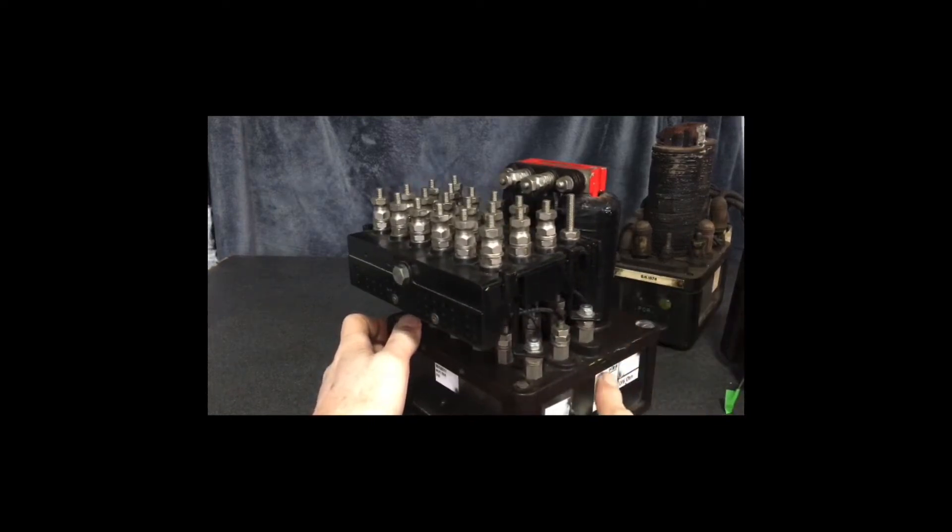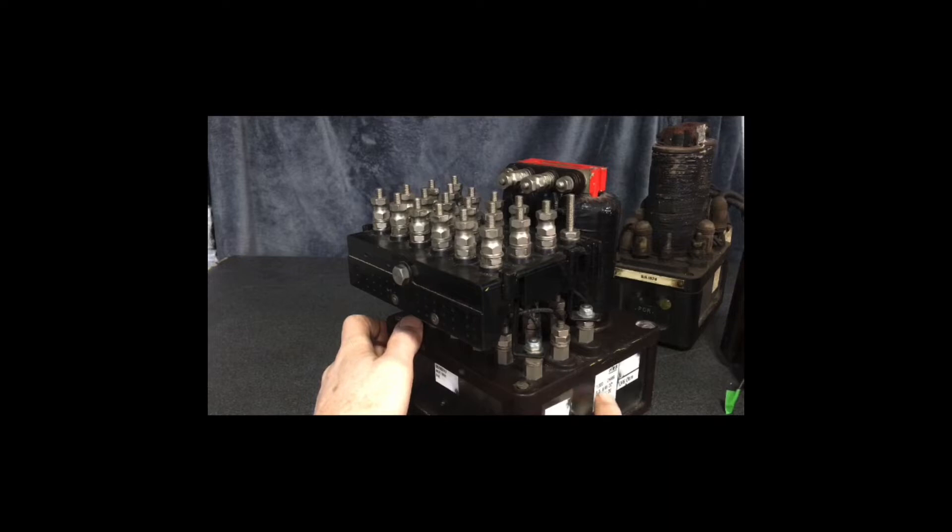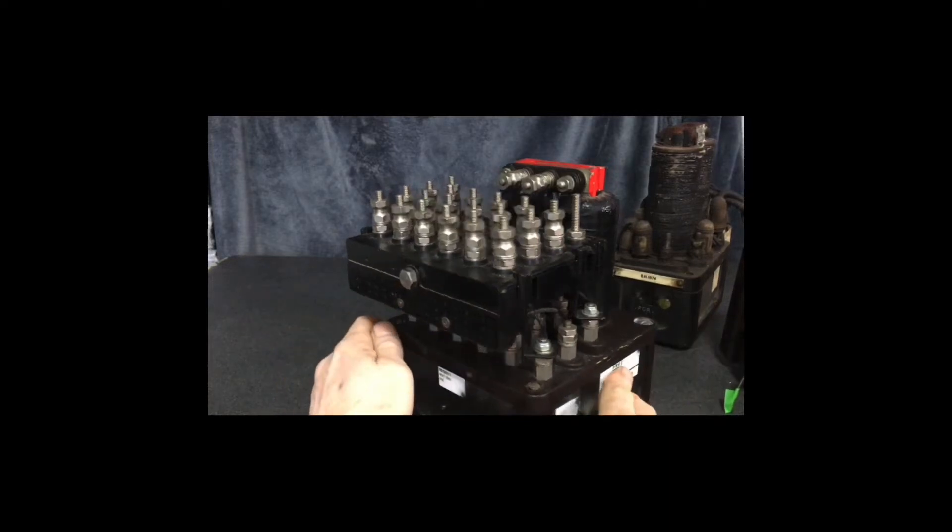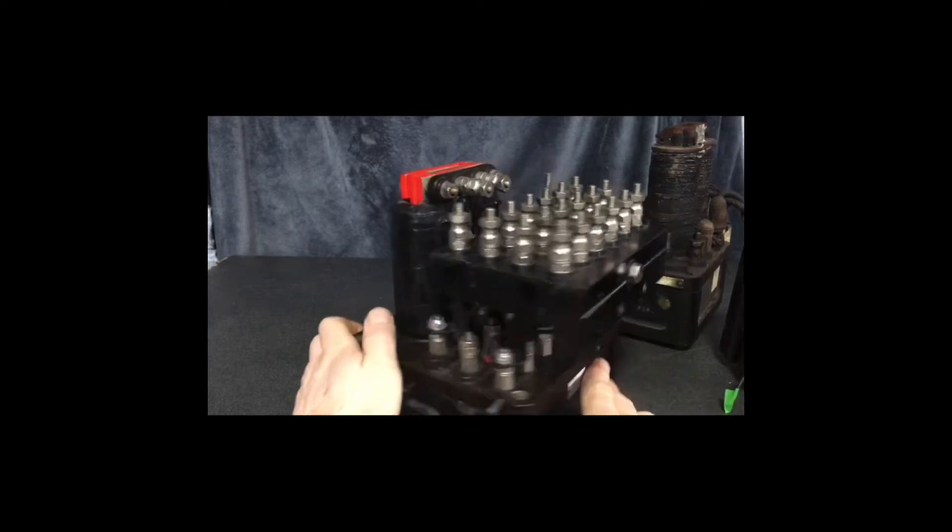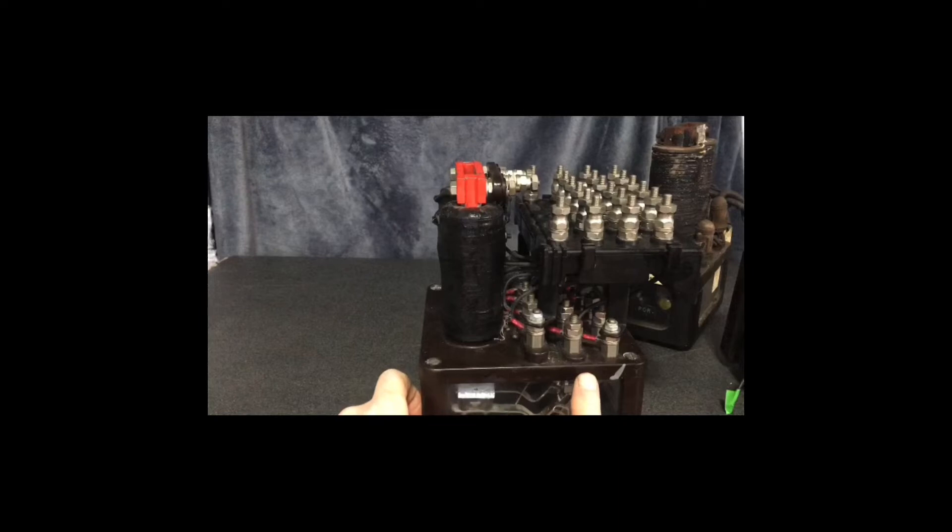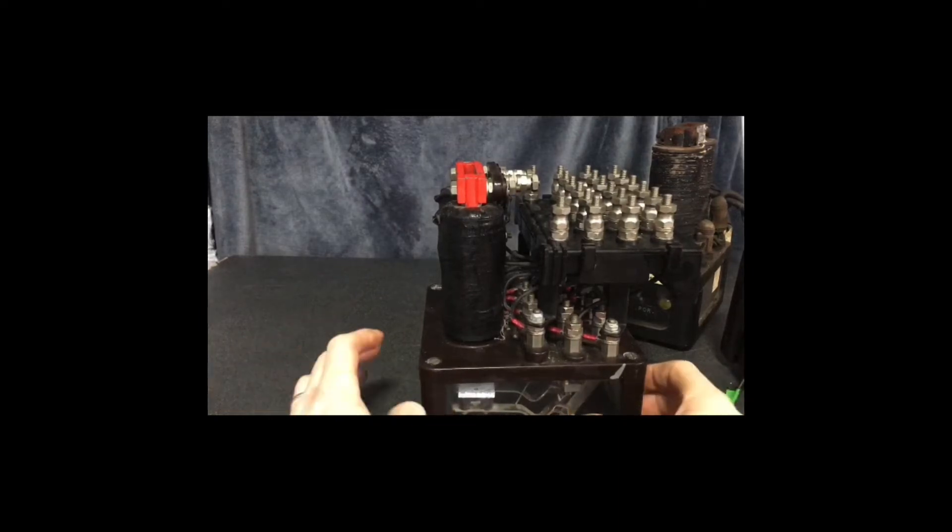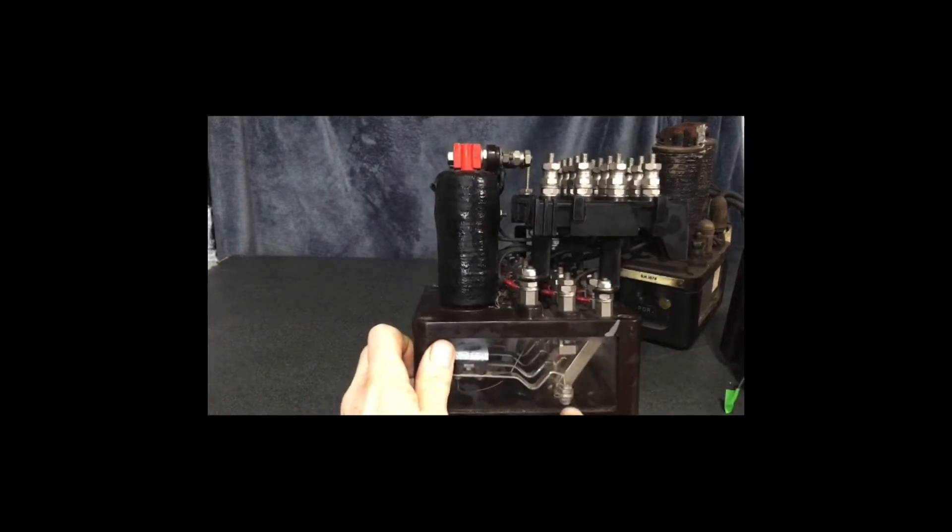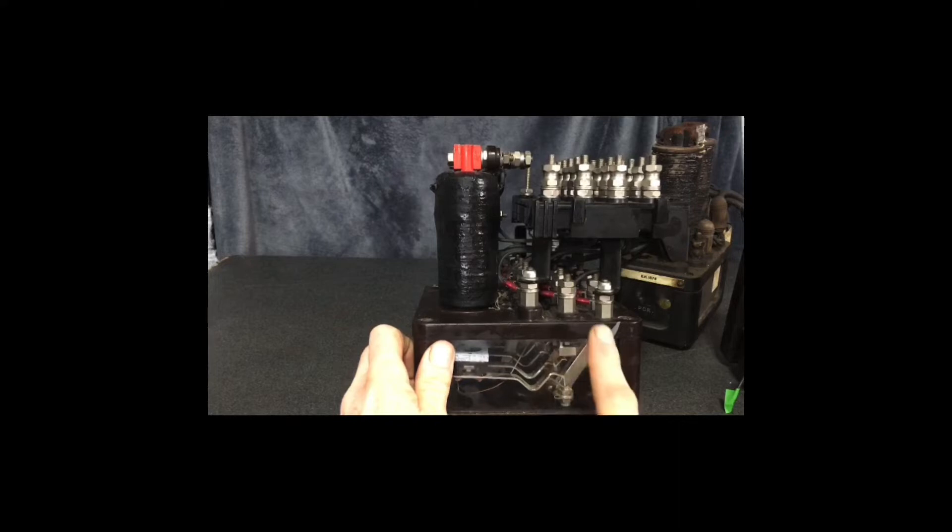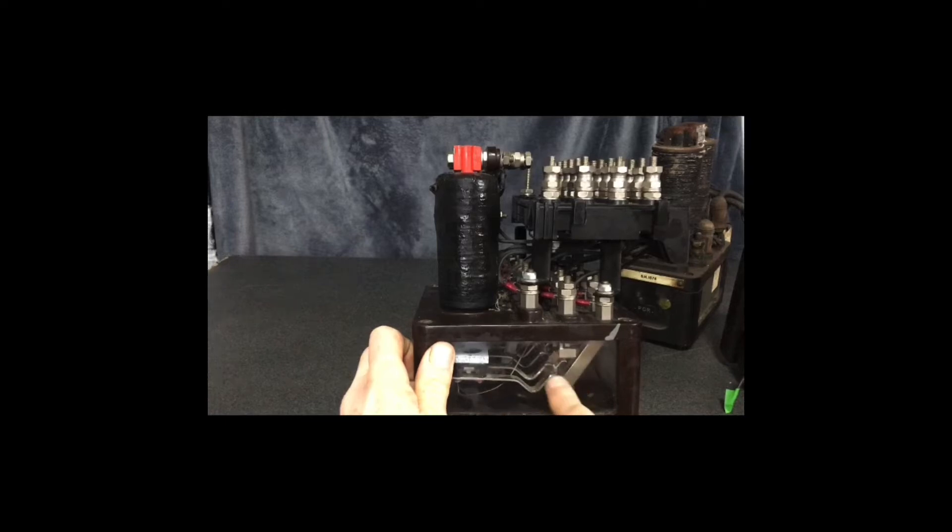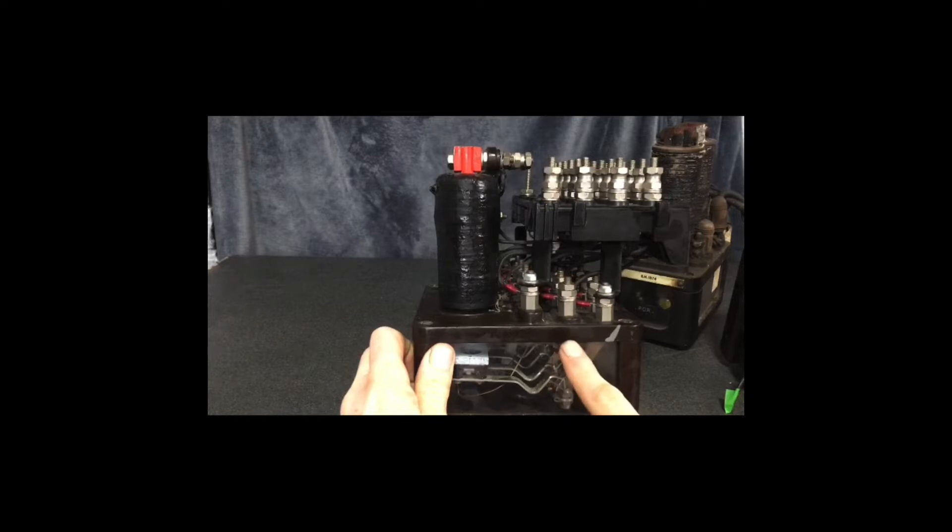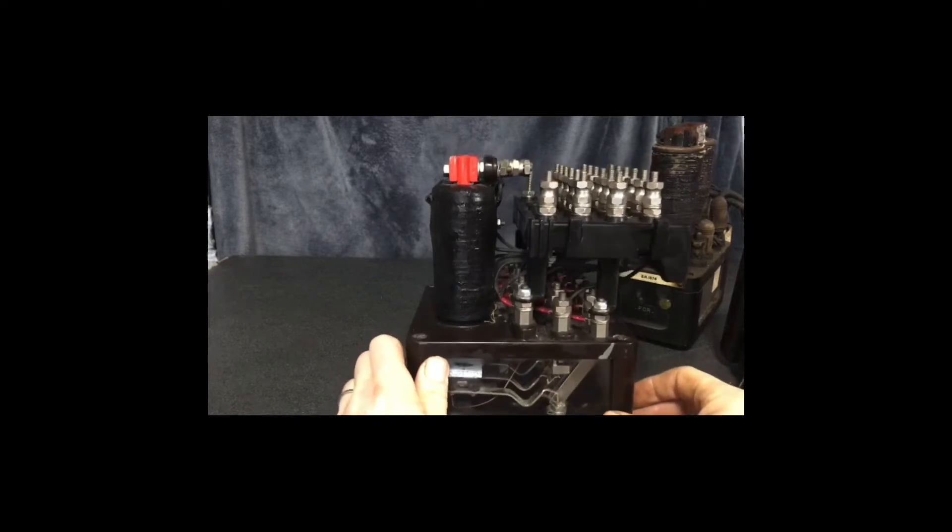On the side it will give you some details. It will give you the resistance of the coils, total resistance, and it will give you the pick up voltage and drop away voltage. The pickup voltage is the voltage at which it will finally pick. The drop away voltage is the voltage at which it will finally disengage, drop away. It is a momentary action because you do not want the front contacts and the back contacts made at exactly the same time. Otherwise you could false feed some circuits. There's a slight springiness in the armature as well. You'll see it when we try it, it'll suddenly pick, and then if we drop the voltage away it will eventually just lose enough voltage to hold its magnetic field and then drop away.